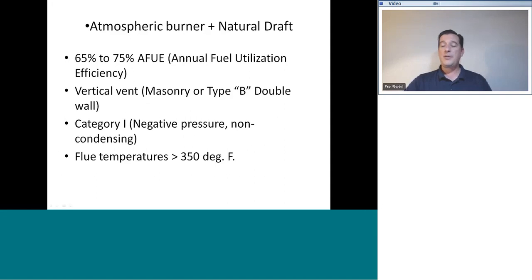All atmospheric burners with natural draft are considered Category 1 appliances. Category 1 means that the vent is under negative pressure, sucking, and it is a non-condensing arrangement. The flue temperatures will be greater than 350 degrees Fahrenheit. Question, are vent liners accepted? Yes, if they are a listed double wall B vent corrugated vent liner, yes.